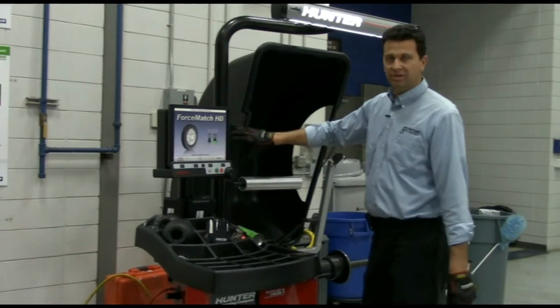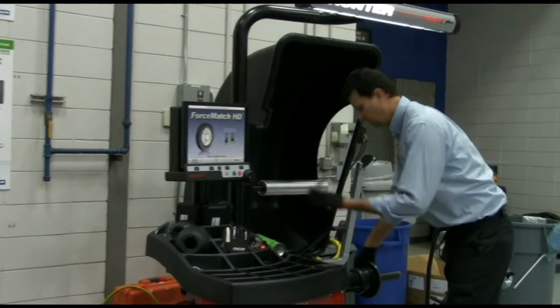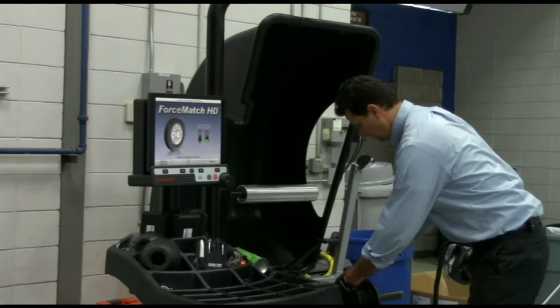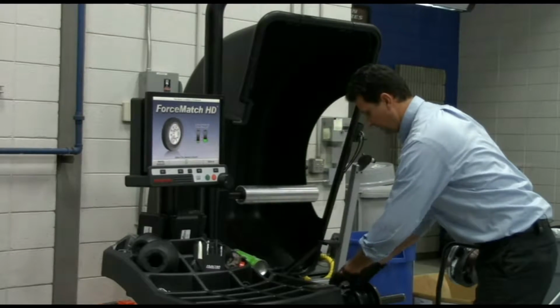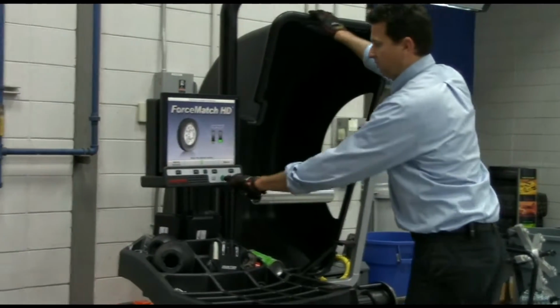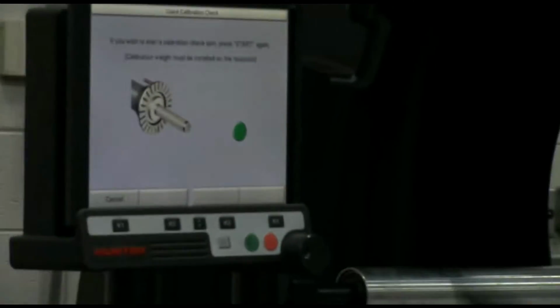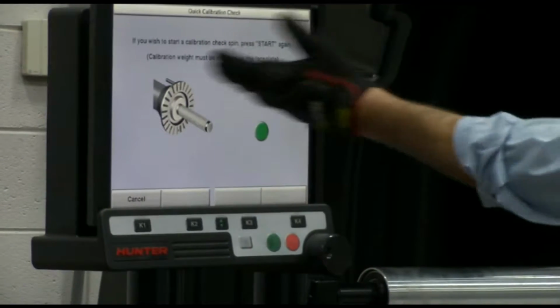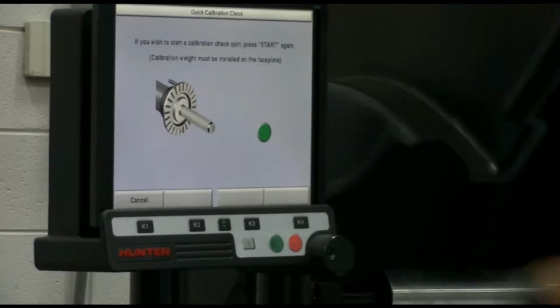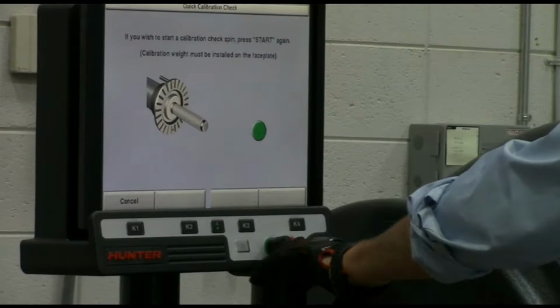This is what the machine looks like when you turn it on. That's your home screen. You take this slug, screw it in either the left side or the right side of the hub. Press your start button. It says if you wish to do a calibration check, lower the hood and press start. So that's what we're going to do. It's going to spin about 15 or 20 seconds. We'll come up with a number off of that, and we'll also see if our weight placement is correct.